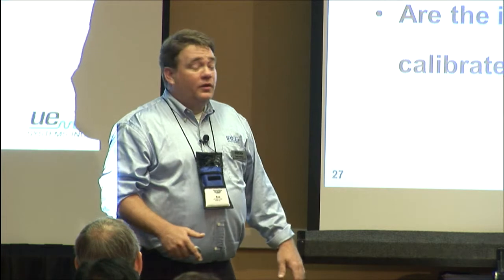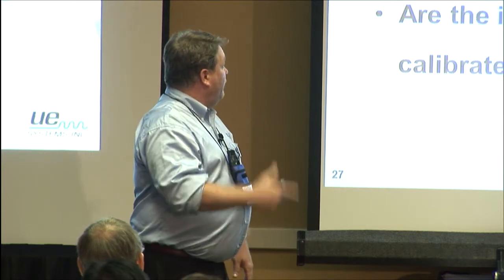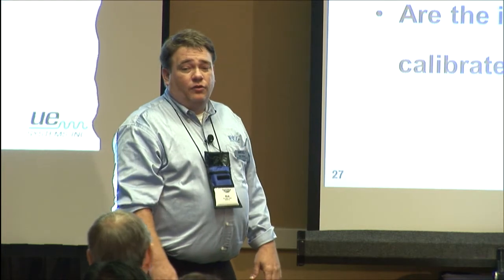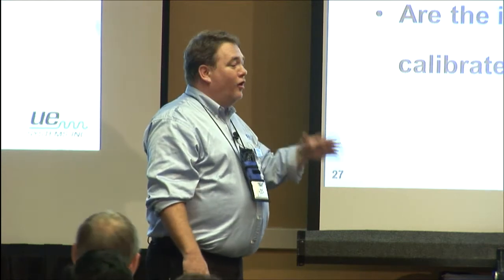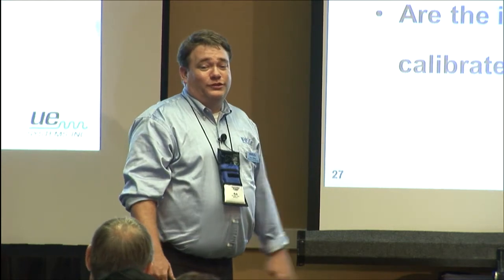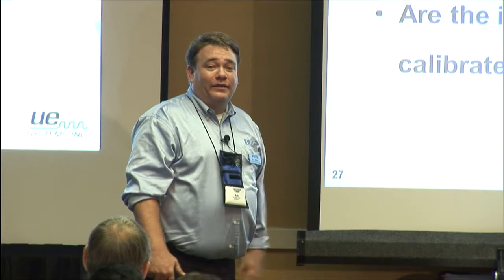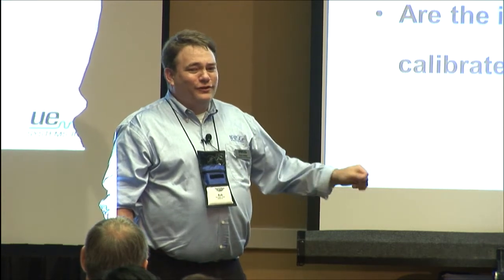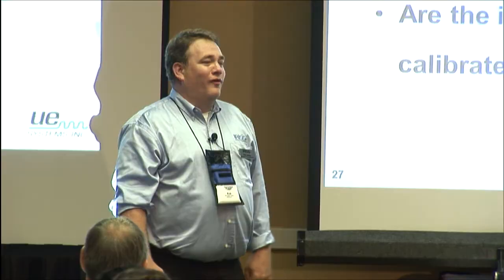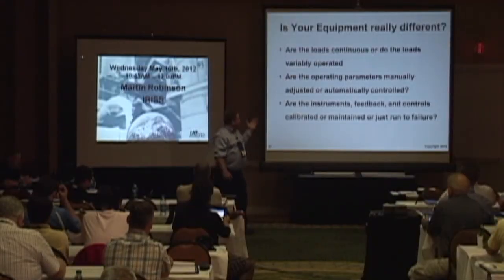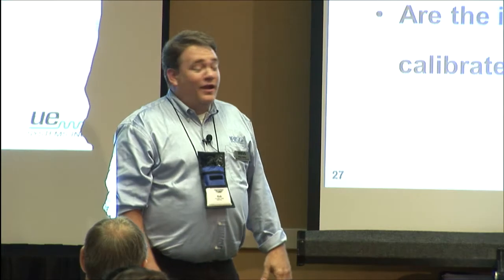Are the operating parameters manually adjusted or automatically controlled? Is there an operator on third shift? Everything that ever breaks happens on third shift - as a guy in a plant, everything breaks on third shift and nobody knows why. 'We didn't do anything wrong, boss.' How are you operating it? Are you loading it up so you don't have to walk out there as often? Are you operating outside the pressure parameters, or is a PLC keeping track of it?